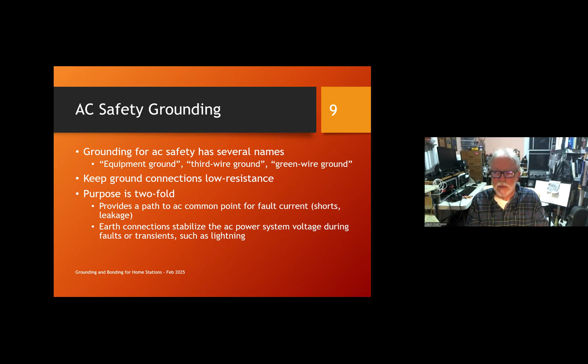It only has two purposes: it provides a path back to the AC common point for fault currents, which shows up also as leakage current if you have degraded insulation or something, and it stabilizes the AC power system voltage during a fault or transient, such as lightning. If you look at your power poles or transformer systems, all of them have some kind of ground connection, which helps the AC power system maintain a stable, well-regulated voltage through all these connections to the earth. But that's the only reason you have equipment grounds; it has nothing to do with lightning protection or RF management.